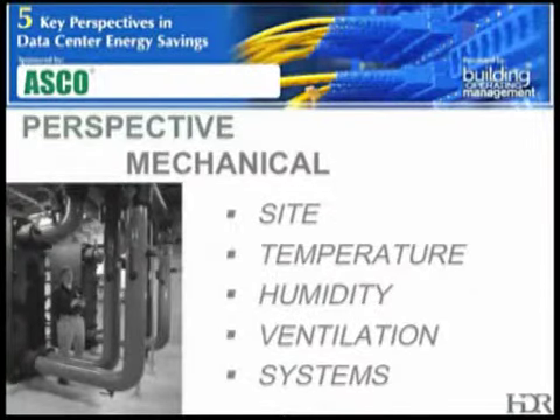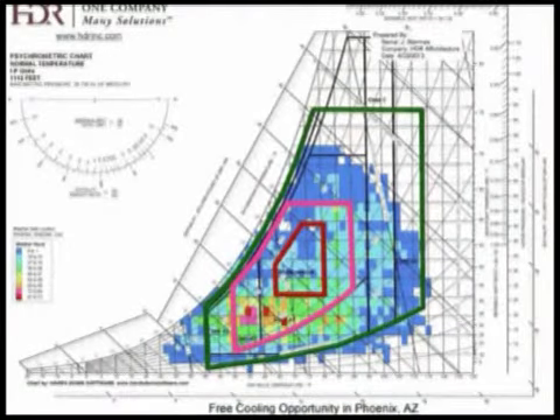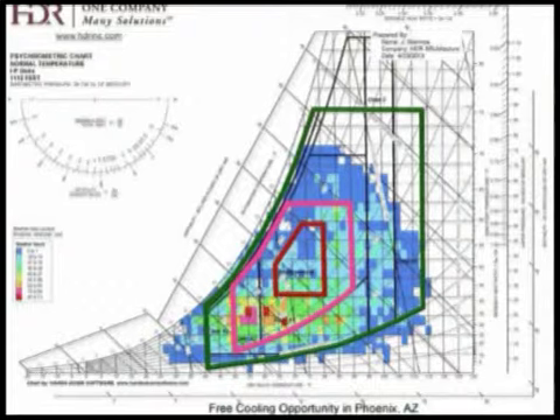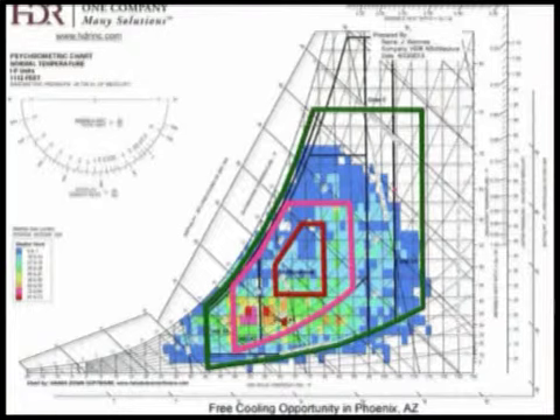Craig talked a little bit earlier about the site conditions, and we definitely want to understand these site conditions in order to be able to use them to our advantage. I think it really begins with an understanding of the site environmental conditions. And I'm not talking about just the standard information that we typically use in other designs, which is dry bulb design temperatures, wet bulb design temperatures. We may even look at extremes, but what we really want to look at in data centers is the range and maybe the concentration of the temperatures and the corresponding relative humidities.